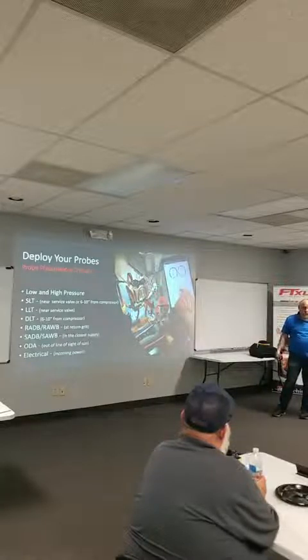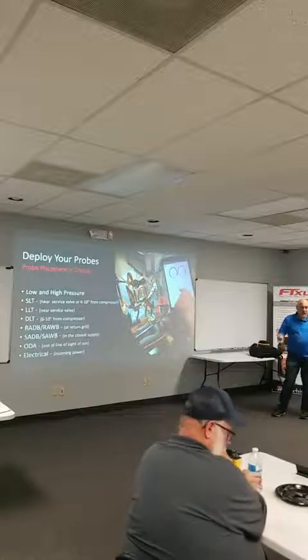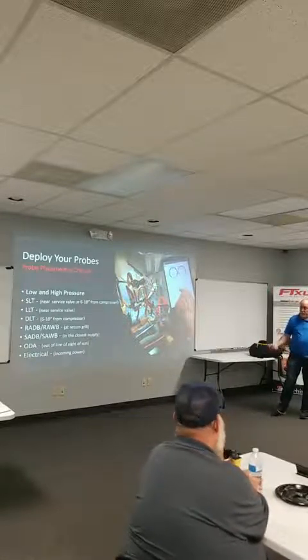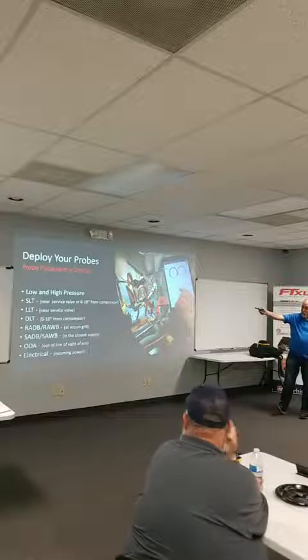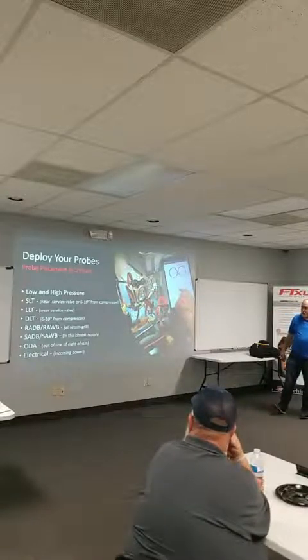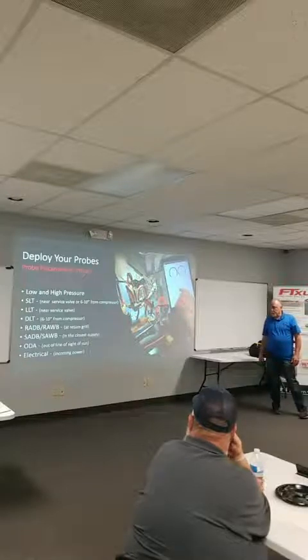You walk in there, you start feeling cold because you have all these open cases that are cold, and it's sucking the heat out of your body, right? Heat is radiant energy, so we need to be far enough away from the compressor that we're not picking up heat. We need to be at the liquid line near the service valve. Discharge line, again, 6 to 10 inches away from the compressor.